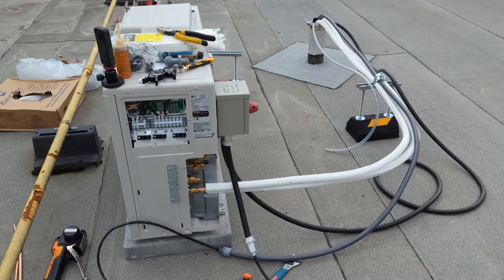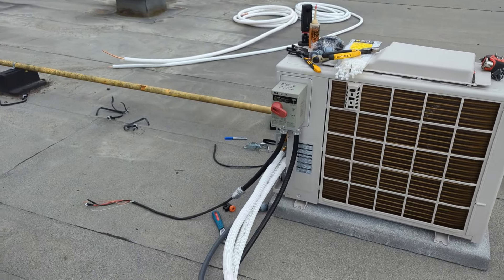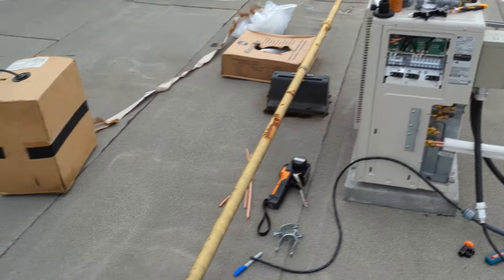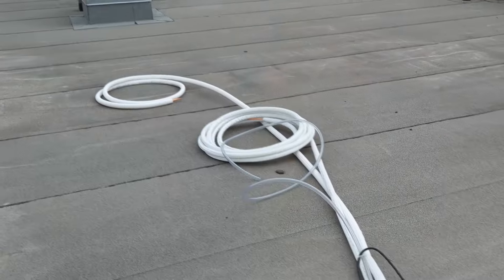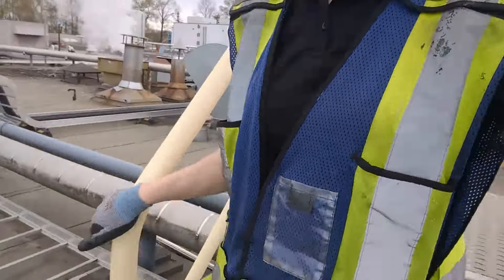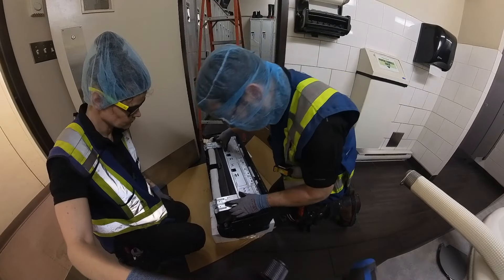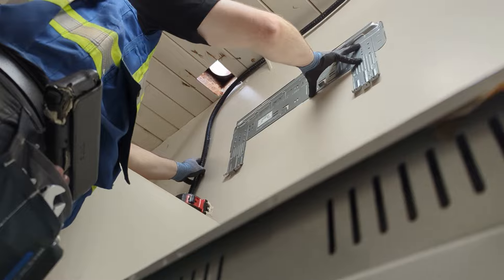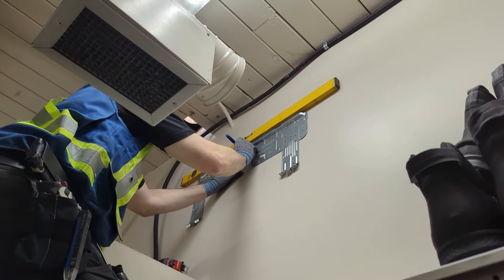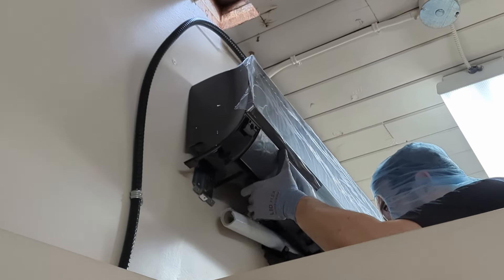That basically leaves just the control cable and power cable to this unit. But instead of doing that, we're going to get started on the second indoor head so that that can at least be done. So we've prepared our line set like we did before, and now I'm going to head back downstairs through this fun little maze and get started on unit number two. Starting with that mounting bracket to make sure we know exactly where that's going to go. This time we're not going to cut a hole through the wall because we're just going to go straight up through the roof jack. So we're just leveling off our mounting bracket and mounting the unit, baby.